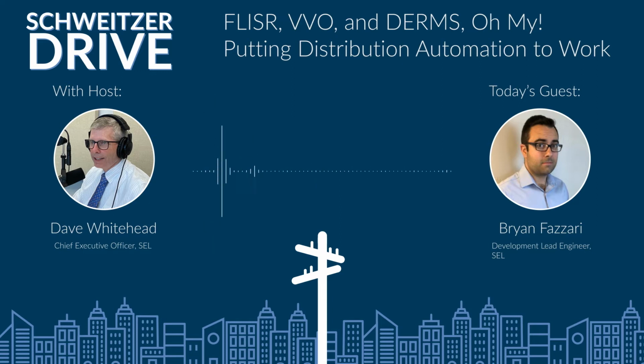In previous podcasts I've discussed protection technologies like traveling wave and other things. Protective relays not only detect faults, they issue commands to circuit breakers to open them up. 80% of all faults are transitory, so the relay waits a little while and the fault eventually burns out. The relay then closes the line back in, and lights come back on. This all happens in a matter of a handful of seconds or so, and in my mind that's a pretty automated process. But it seems like there's more to this automation stuff, especially from you automation engineers, than the simple automated system I just described with the relay. So Bryan, how do you define automation?